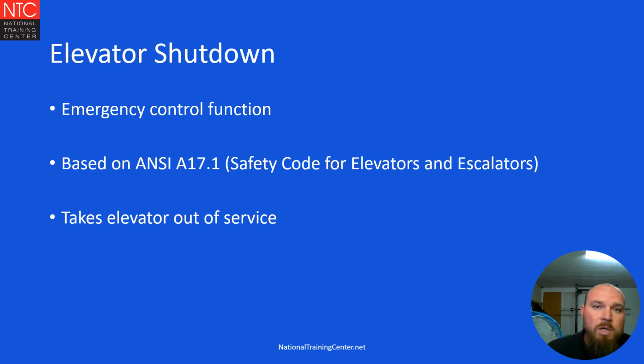If your elevator hoistway has sprinklers, you're going to need shutdown. So let's take 2 minutes to learn more about elevator shutdown. First and foremost, elevator shutdown is an emergency control function. It is going to be there to enhance the life safety of the building. Its basis comes from ANSI A17.1, which is the safety code for elevators and escalators. And simply put, what shutdown does is it takes the elevator out of service.